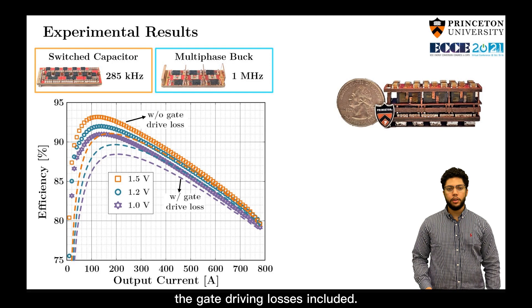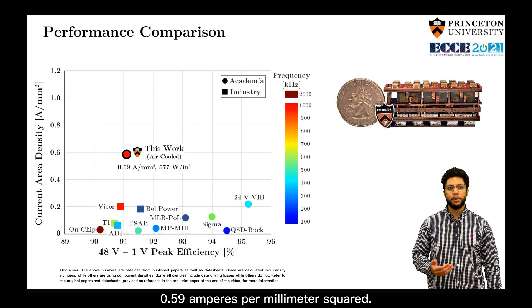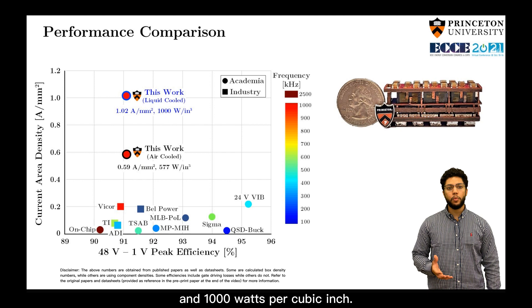We benchmarked our converter with other 48 volt to one volt converters, both from academia as well as from industry, and ours maintains a good efficiency while achieving a density of 0.59 amps per millimeter squared. With the liquid cooling setup, we achieve 1 amp per millimeter squared and 1000 watts per cubic inch.